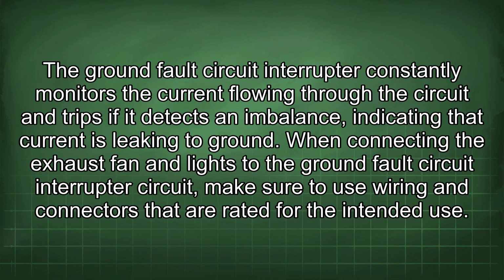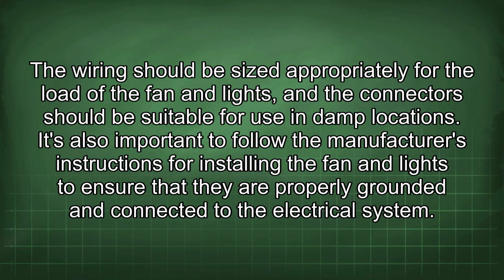When connecting the exhaust fan and lights to the ground fault circuit interrupter circuit, make sure to use wiring and connectors that are rated for the intended use. The wiring should be sized appropriately for the load of the fan and lights, and the connectors should be suitable for use in damp locations. It's also important to follow the manufacturer's instructions for installing the fan and lights to ensure that they are properly grounded and connected to the electrical system.